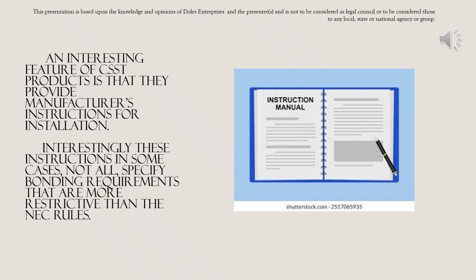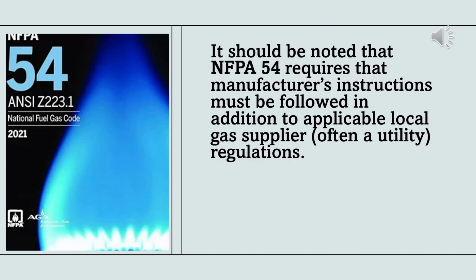So the inspector's now left with having to decide, okay, I've got CSST piping in this home, so what do I do? Well, you're going to have the manufacturer's installation instructions. I think this is going to go the way of truss design drawings. We're going to have the documents available on site for the inspector when they go out to look at everything. NFPA 54 is the National Fuel Gas Code, and it should be noted that NFPA 54 requires that manufacturer's installation instructions must be followed in addition to local codes, often from the utility and the gas supplier and their regulations.